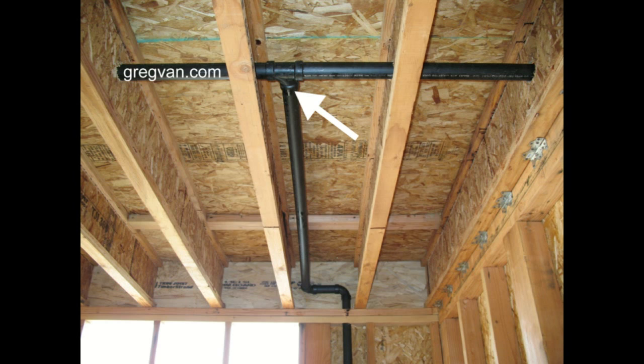So three inch, two inch, and inch and a half pipes are going to need to slope a quarter of an inch per foot when you're running them horizontal like the picture here.